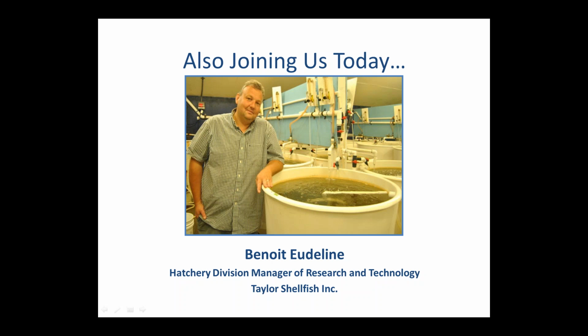And finally, I'd like to give a couple of points that we have learned over the years about the Durafet probes. The first one is about temperature compensation. I think it's important to note that for a commercial user like us, the temperature probe used for temperature compensation and measurement is located inside the body of the probe itself, about 1 inch above the FET sensor, which basically means that the temperature is slow to respond to temperature changes.